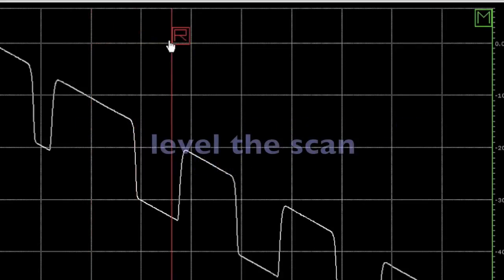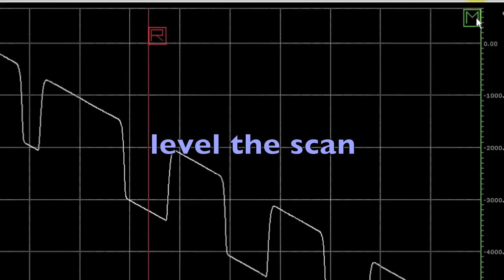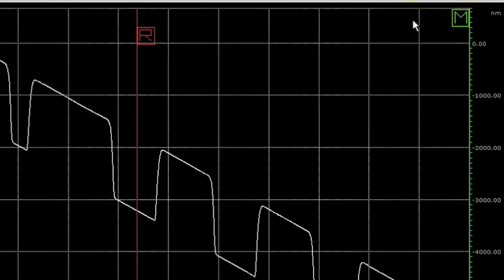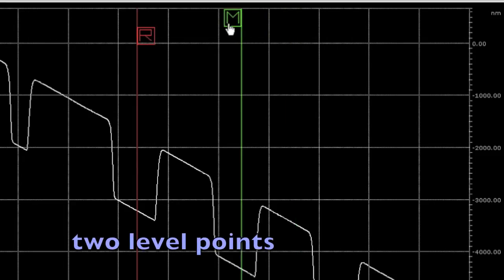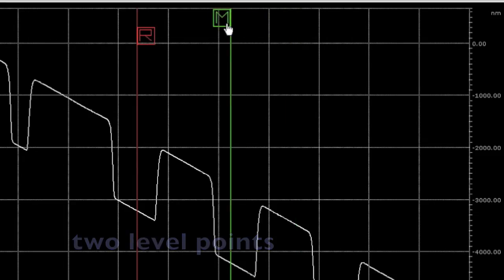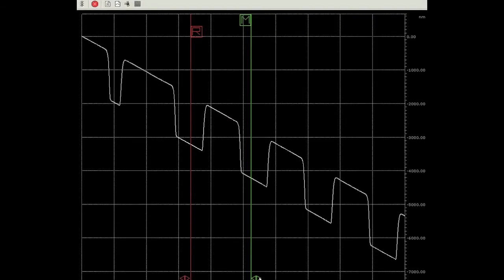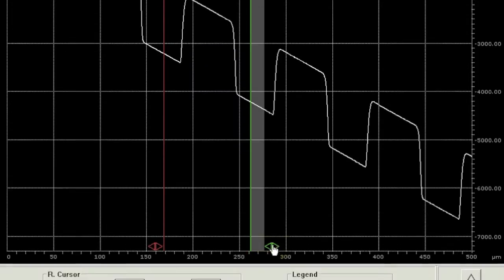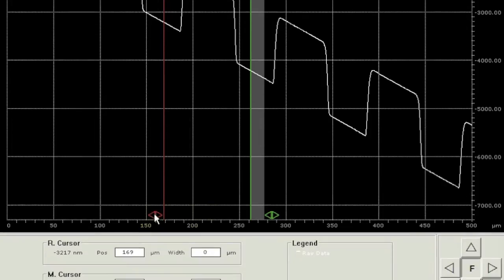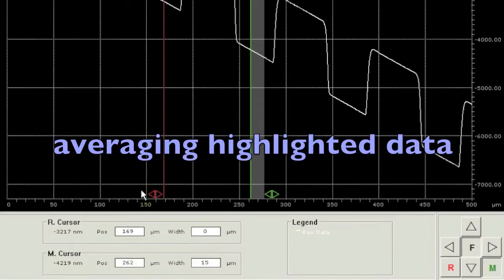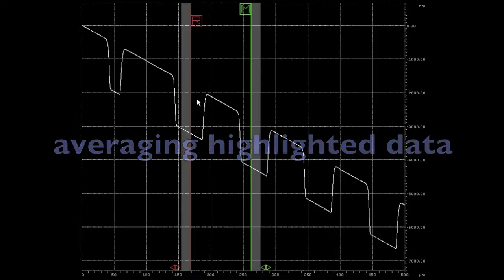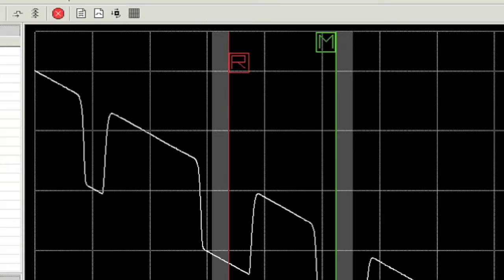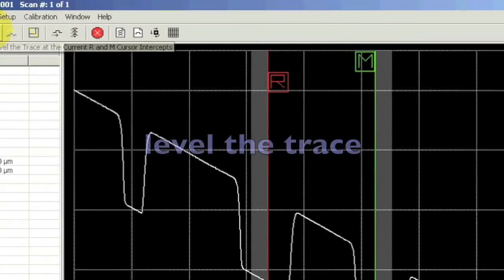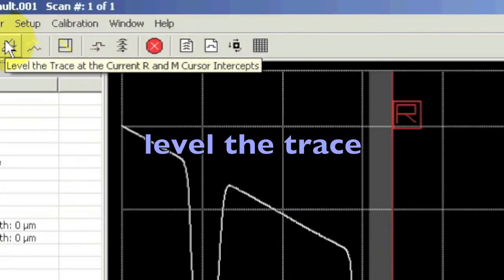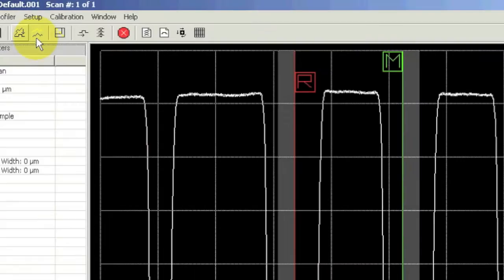The first thing to do is level the scan. To do this, we first need to move the R and M markers to two different points of the scan, which we assume to be level. Because this sample is photoresist patterned above silicon, we can assume that the low points are polished silicon and thus level. Using these arrows, we can spread the width of the markers. This has the effect of averaging the highlighted lateral data points. Now we can click on this icon, Trace Level, to level the trace at the current R and M intercepts. Once leveled, we can take some measurements.